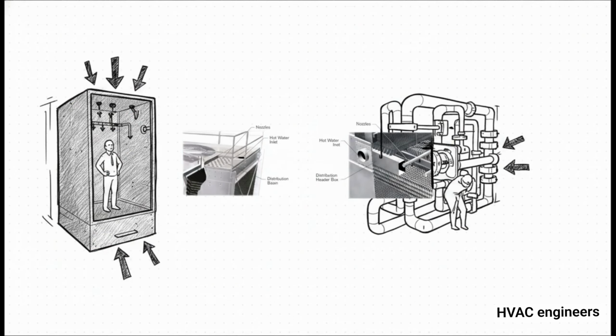Let's look at how the water actually moves. With a crossflow gravity basin, the water gets pumped up exactly once, and gravity does the rest of the work feeding the nozzles. It's this open, super easy to access space where a maintenance worker can literally just stand up inside. Meanwhile, the counterflow design uses a pressurized header box to shove water through branch arms and nozzles. It's highly effective for sure, but the working space inside for maintenance is incredibly cramped and pretty complicated.